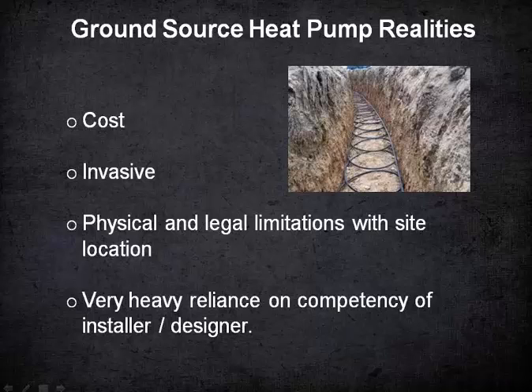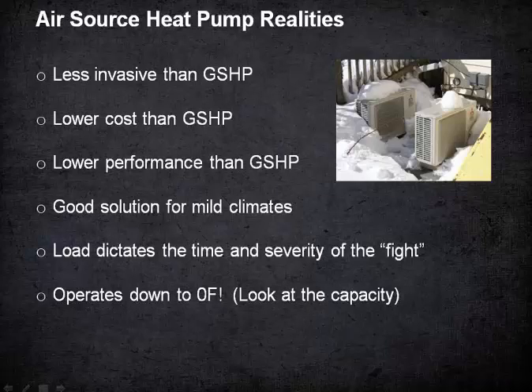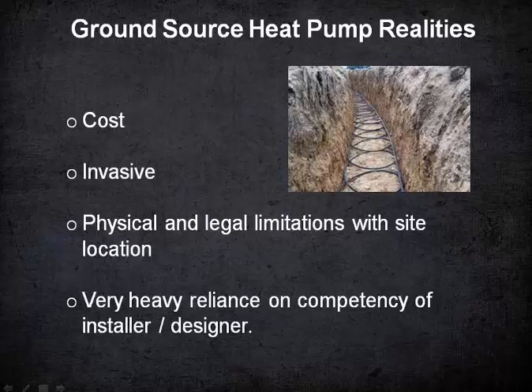And in speaking to some other international ground source heat pump people, I recommended that they put a perforated Tremie pipe into that trench so that if they in fact do lose their moisture because of drought or whatever, they have an opportunity of being able to go back in and recharge at least some of the moisture in that thing to give them a better bite on Mother Earth. But yeah, that's definitely a problem. Absolutely.